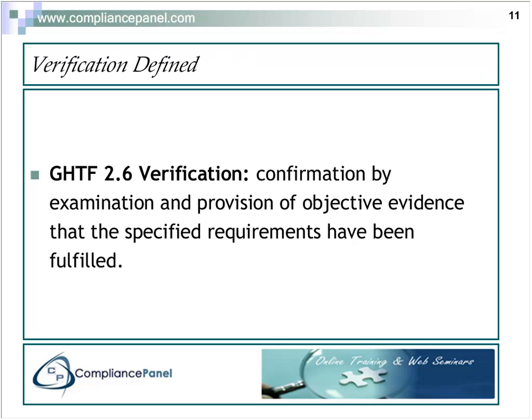Now, in the GHTF document also, another definition is verification, and that's confirmation by examination and provision of objective evidence that the specified requirements have been met or fulfilled. So again, we have to provide objective evidence, and the process that we use is some type of examination that can be an inspection, a test, or other observation that we can demonstrate that a requirement for a particular product has been met. And of course, we talk about design verification.